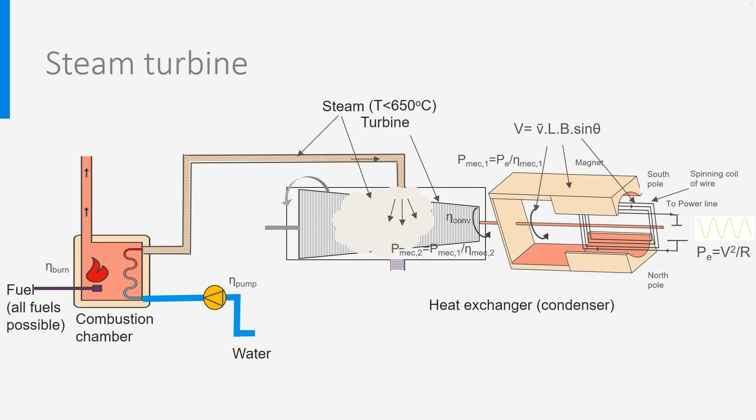Let's look at their efficiency now. The efficiency of the boiler is high, as usual, around 0.96. As the turbine is not connected to a compressor, but only to the generator, we could expect it to have a higher efficiency, eta-conv, than the gas turbine. However, the temperature of the steam, and therefore the energy it contains, is much less than in a gas turbine.